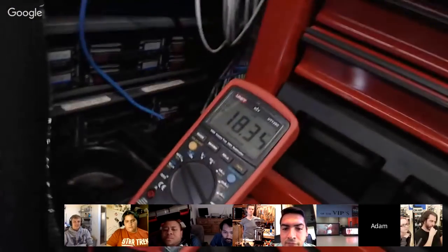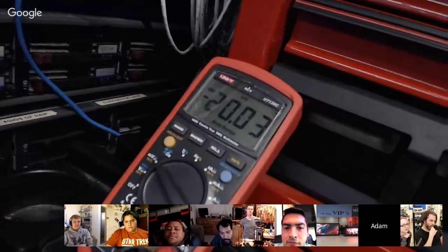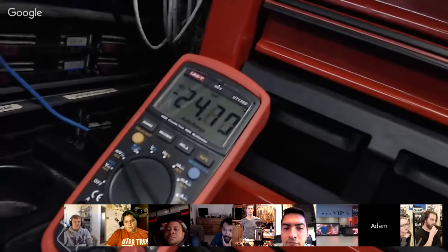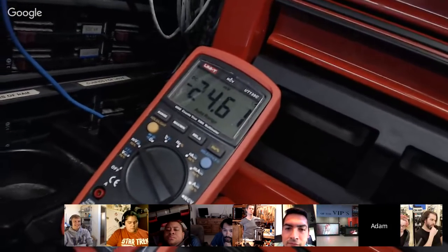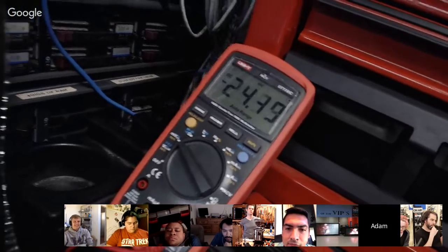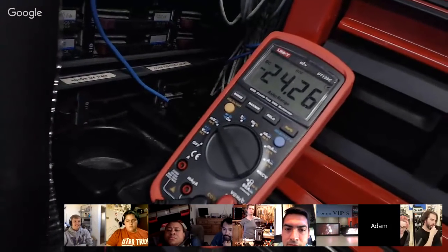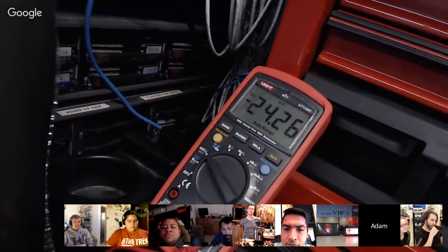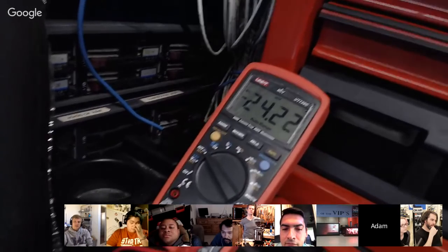So I've got that hooked up to a multimeter, and I'm going to open the valve right now. If I open the valve, you can see on the multimeter that the voltage starts to increase, which indicates that there's a giant leak somewhere. So instead of having to buy a new high vacuum gauge, which is relatively expensive, I figured out how to find test points in the back of this thing so I can start diagnosis. After this, I'm basically going to be spraying helium or hydrogen all around the different vents. And if you get the really light gases close to one of the leaks, then you'll see a spike in vacuum pressure.